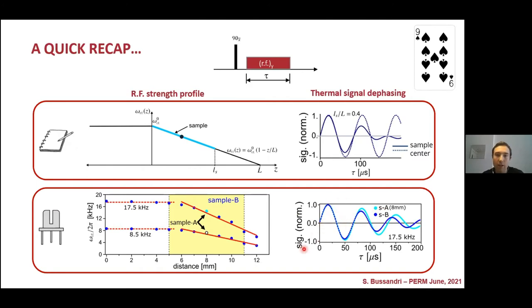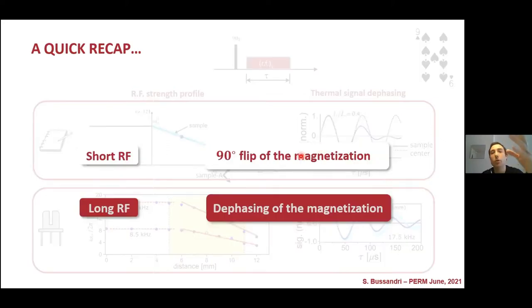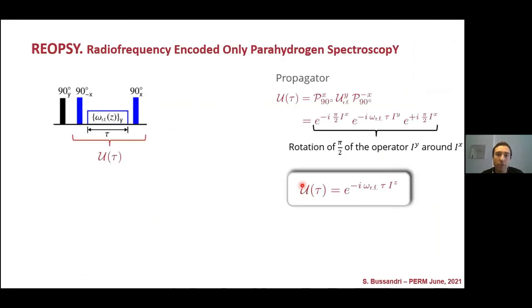What we saw, what we can confirm from these experiments and from the calculation is that monitoring and controlling the length of the sample, in short RF we can make a 90 degree flip of the magnetization and long RF produce a dephasing of the magnetization. This great control of the spin evolution during RF allows us to design the following sequence.